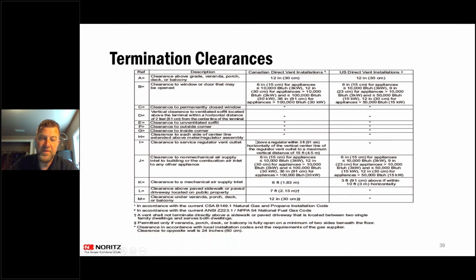But going through this, so unventilated soffit, we don't have a clearance. Clearance to the outside of a corner of a house, all these ones we do not have clearances to. So it would just go off of the local code, which I'll leave to, as I'm sure all of you know, some crazy interpretations. But one thing that I want to emphasize with everybody on this, because I get a lot of calls on this, is this J. So J is clearance to a non-mechanical air supply inlet to a building or combustion air inlet to any other appliance. So we do a lot with new construction.